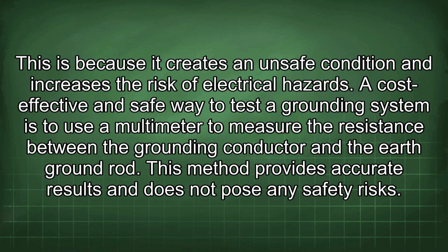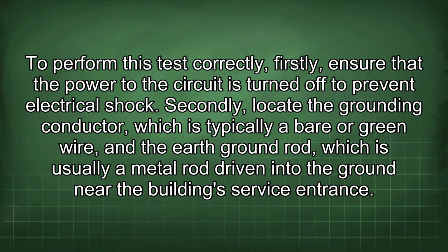A cost-effective and safe way to test a grounding system is to use a multimeter to measure the resistance between the grounding conductor and the earth ground rod. This method provides accurate results and does not pose any safety risks. To perform this test correctly, firstly, ensure that the power to the circuit is turned off to prevent electrical shock. Secondly, locate the grounding conductor, which is typically a bare or green wire, and the earth ground rod, which is usually a metal rod driven into the ground near the building's service entrance.